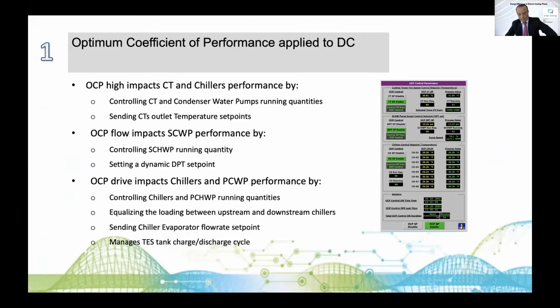We're going to be talking about this solution, OCP, optimum coefficient of performance. OCP is an optimizer, meaning that it communicates with the plant's PLC. It doesn't substitute the plant's PLC. It's been specifically developed for district cooling plants, with MENA region district cooling plant conditions in mind. The main component is dealing with the heat rejection apparatus, where we're trying to find a set point that will reduce the plant's consumption, going a little bit further than the usual floating head pressure that we see in relatively modern plants.